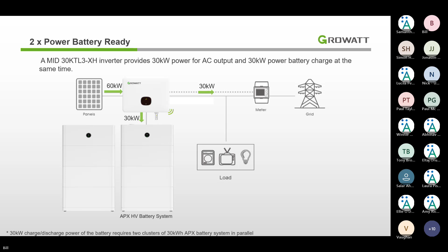But the biggest difference between MID and MOD is not just the power rate, it also comes with two battery ports. That means normally the APX can reach 30 kilowatt hour, but for the MID, you can even connect 60 kilowatt hour, which is 12 batteries. That's because when you want to achieve the maximum charge and discharge rate of 30 kilowatt from the inverter, you will need at least 60 kilowatt hour of batteries. That means 12 batteries in total.